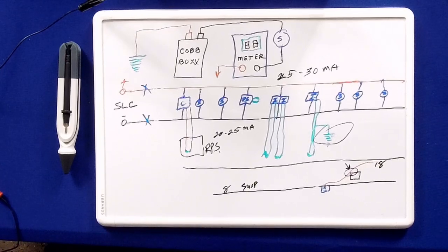Now, most HVAC units you can turn off individually, most of the time through a computer these days, because you have very advanced HVAC systems. So I asked the technician there, the maintenance guy, I said, hey, can you start turning off some of these HVAC units? Because HVAC units are notorious for causing the vibration that wears in the wire. I at one point found a damaged wire because they had run a metal greenfield to a furnace, run the normal, very thin fire cable, and it actually vibrated enough that when I pulled that wire out of that greenfield, you could see every single spot where the rings of the greenfield wore in to the fire cable.